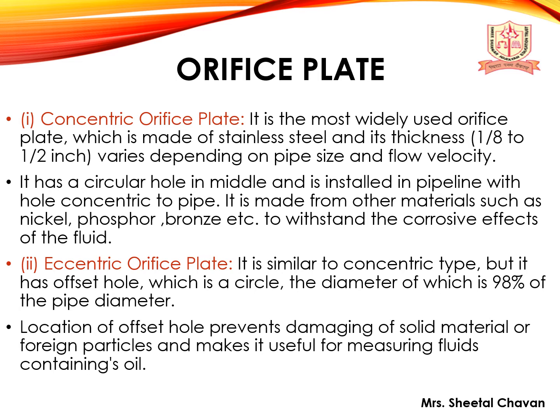The first type is the concentric orifice plate, which is the most widely used. It is made of stainless steel with a thickness of 1/8 to 1/2 inches, varying depending on pipe size and flow velocity. It has a circular hole in the middle and is installed in a pipeline with the hole concentric to the pipe. It can also be made from other materials such as nickel, phosphor bronze to withstand corrosive effects of the fluid.